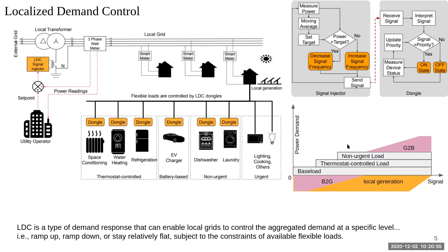So why can we do this? Because some loads are flexible. So we define flexibility of the load based on their operating conditions. For cooling, we have this setup. The main formula for flexibility is just the flexibility space divided by the total operation horizon. For heating it is the reverse. While for electric vehicle charging, we consider the time of use of the electric vehicle and the target state of charge. So the algorithm should be able to predict how long the battery will take to reach the target charge and then use that remaining time as the flexibility space so it can delay its charging. For the non-urgent loads, it's quite similar to the electric vehicle, but it uses the time for the latest finish of its job. For the battery storage, the flexibility is based on the state of charge.